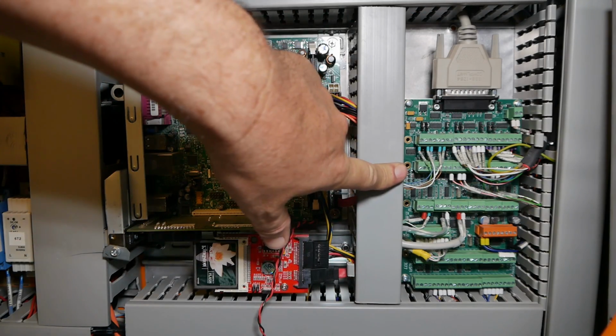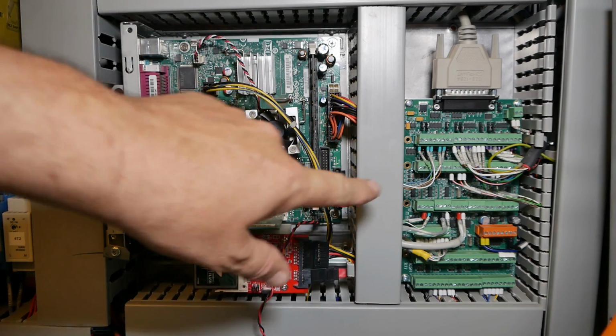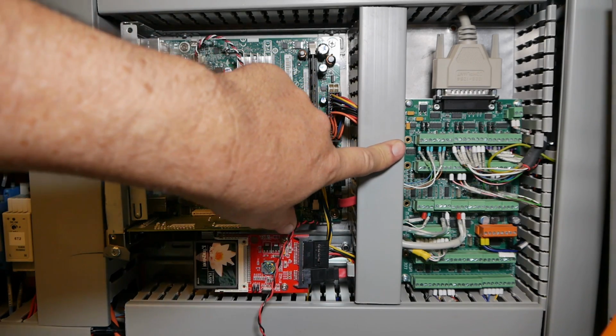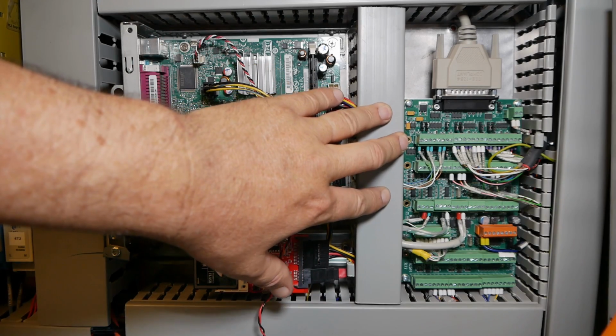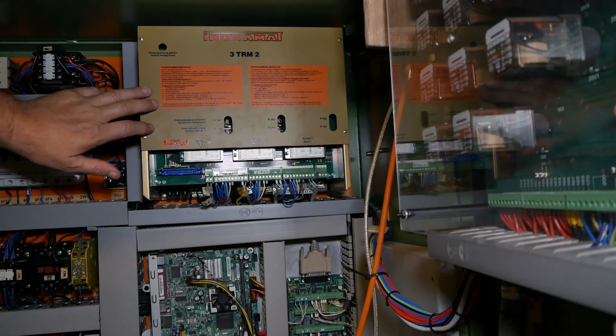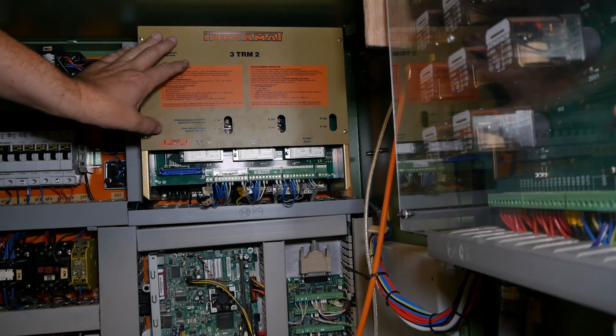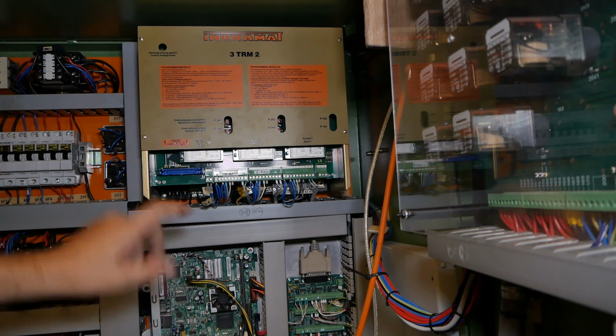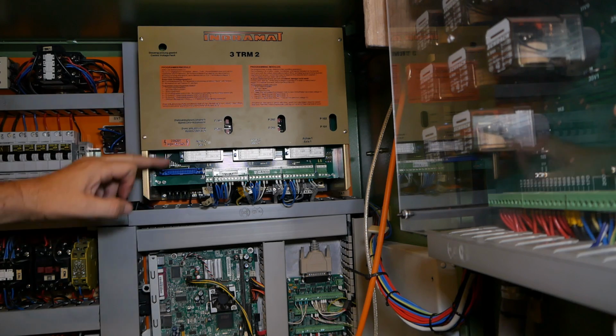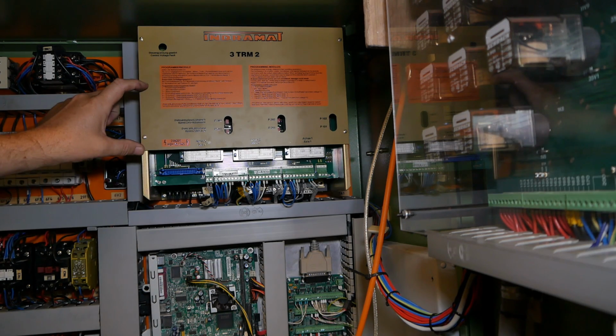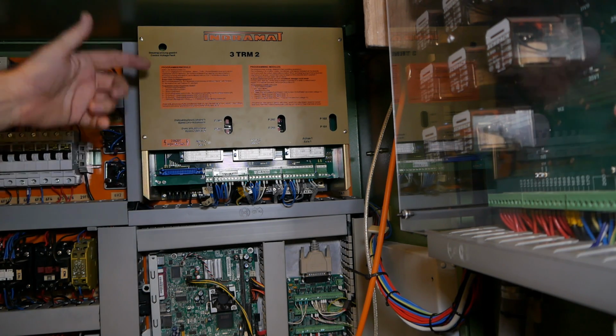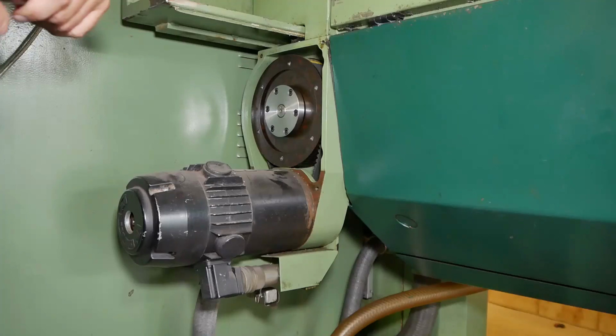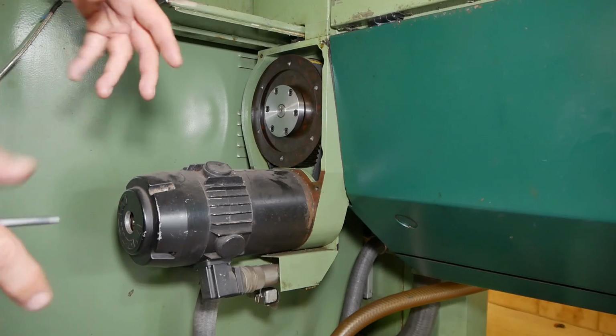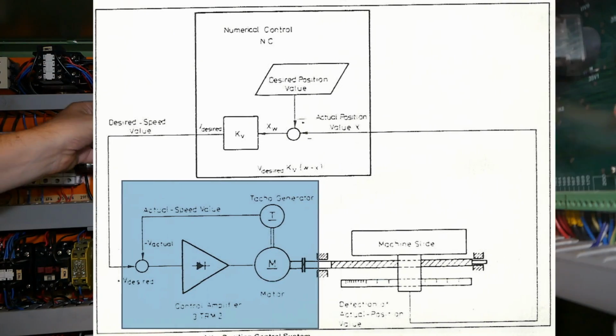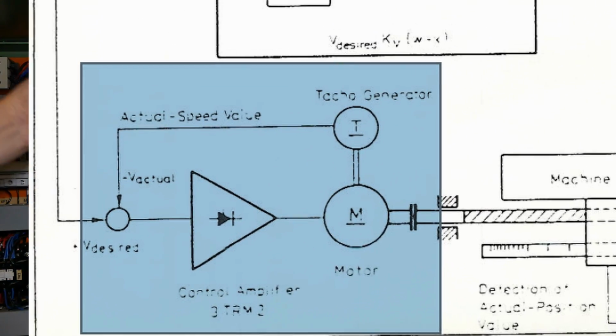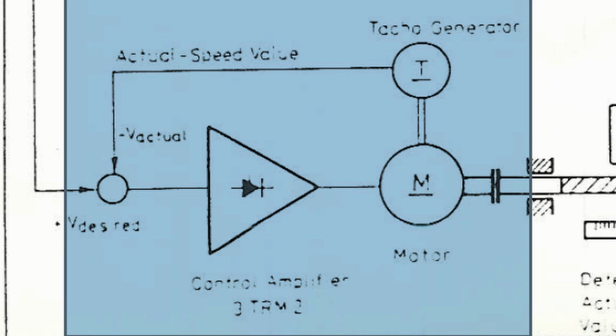And this is a 7i77. Now the cool thing about this is it's the interface for analog controllers for your drivers. So up here above the brain is the Indramat. This is just an old analog DC driver unit using plus 10 volt through to minus 10 volt analog signals, converts that into a velocity command for the motor, which are just big DC motors, DC brushed servos. The motors have got resolvers on them, so the feedback loop for velocity is closed within the Indramat.